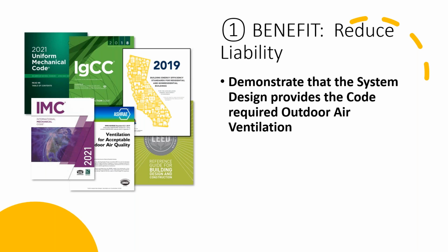So how can you comply with these codes? Well, by measuring airflow, you can demonstrate that the system design provides the code required outdoor air ventilation to the space. And all of these are rate-based standards. So what does that mean? You're having to design to a certain rate. So how do you demonstrate you're achieving that standard? You have to measure.